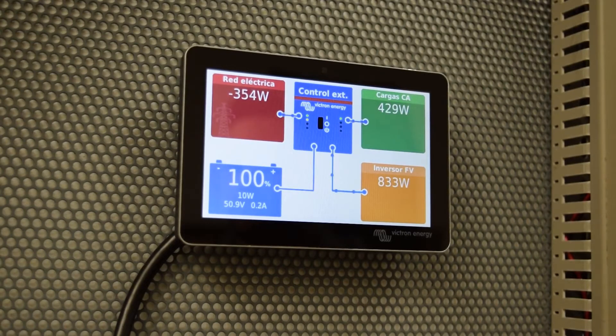We are exporting to the grid approximately 360 watts. Now when I turn down the circuit breaker, we're going to lose the grid. The battery is 100% charged and can't be charged any further. To prevent it from being overcharged, the Victron with the frequency trimming will regulate the power that the inverter generates and adjust it to the consumption of our loads.